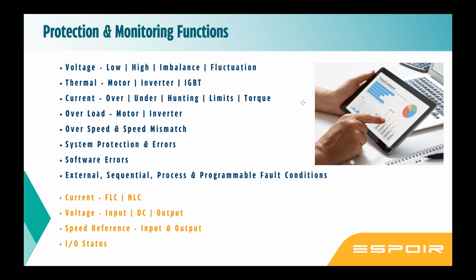Then there are system protection features, and software protection features are available, which will report a control card error, maybe a version error, which sometimes happens. You can do external fault simulation, external fault integration. Which is like you are probing the system. You have to create external fault inputs. Say if a particular motor is off, this system should be shut off. So you need to take the NO/NC contact of that drive and then give the run command through that, or give some status input. It can be sequential. It can be independent. You can set certain process input sequences also.